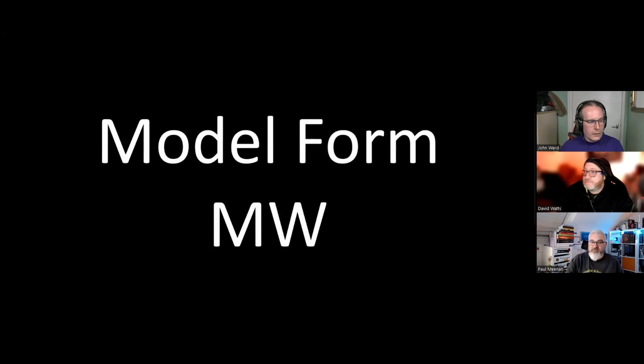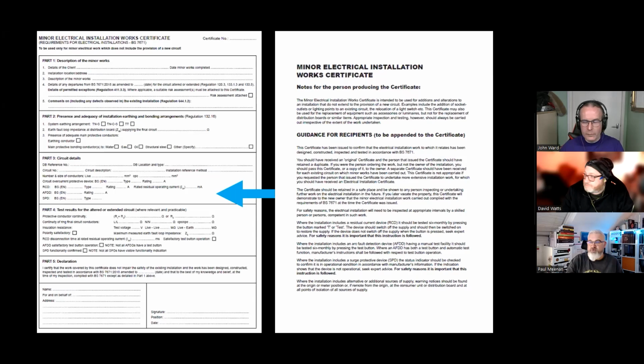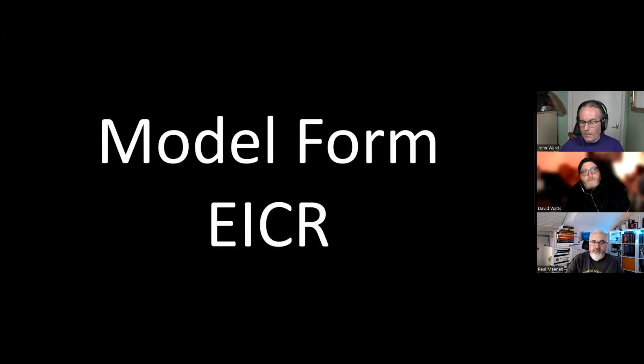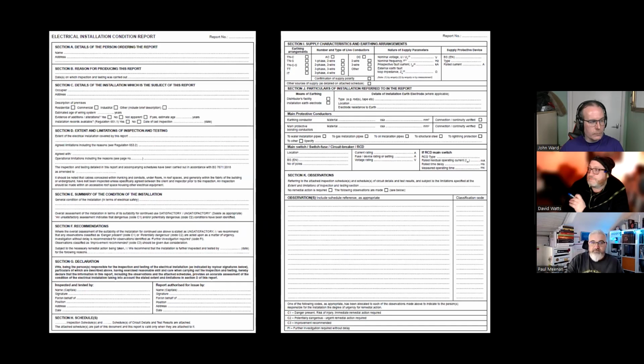There is then the model form for minor works. There's more guidance at the end of all these forms, by the way, that's been updated. But I love the minor works certificate because it's really simple. Description, what you've done, presence and adequacy of earthing and bonding, the circuit you're working on, details. They've added RCD, AFDD and SPD in there, which is great. They've also asked for your insulation resistance test voltage. It's that important now. They want you to declare the test voltage. So if you don't declare 500 volts, you corner cutter you. It's very important.